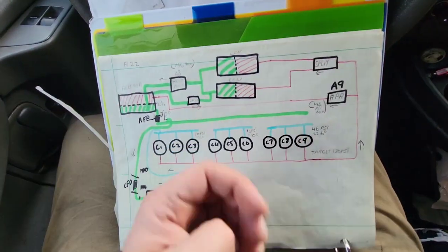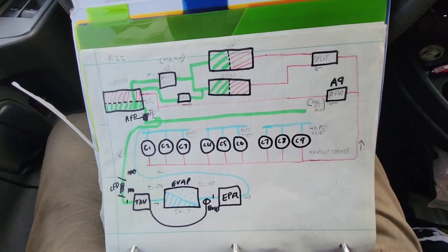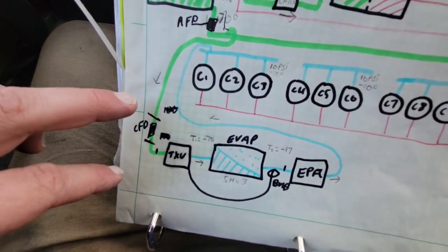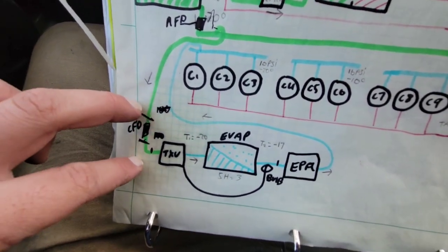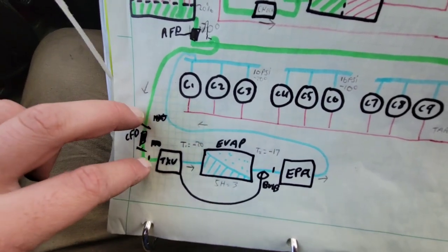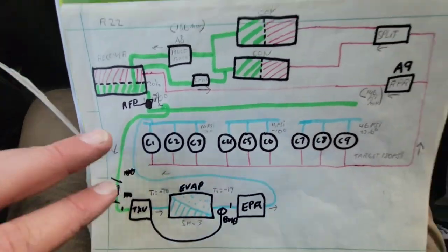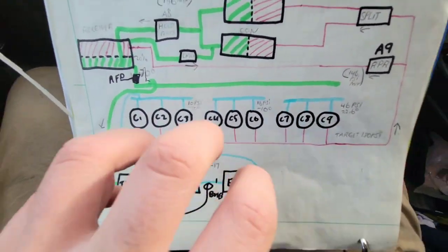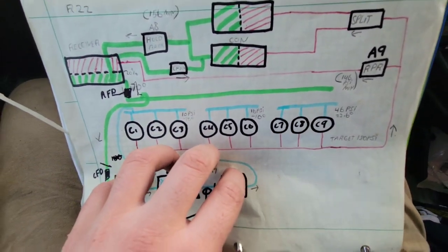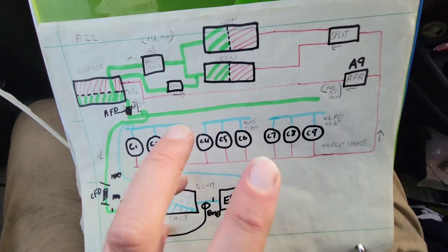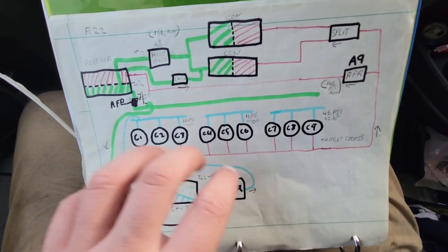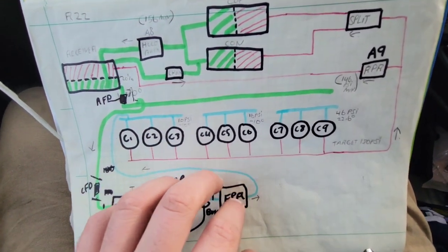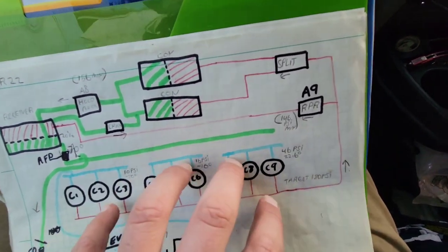Because if you're not flowing refrigerant properly, you can actually get a temperature difference across this filter dryer, or a pressure differential across this filter dryer, just because there's not a high enough pressure from the rack. So your case will show you, oh, I have all this stuff going wrong with me. But in reality, it's fine. It's just you haven't addressed your rack yet.